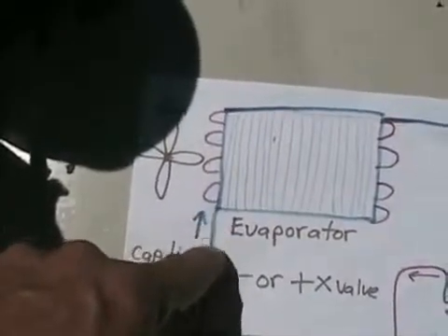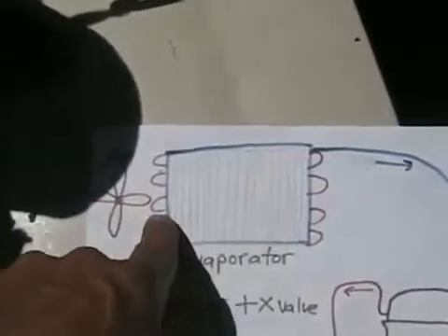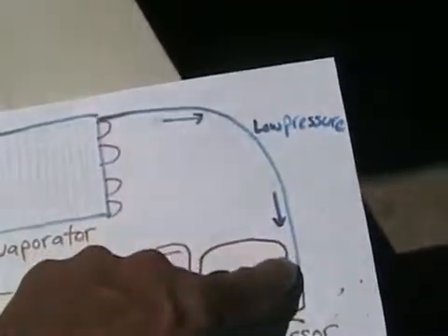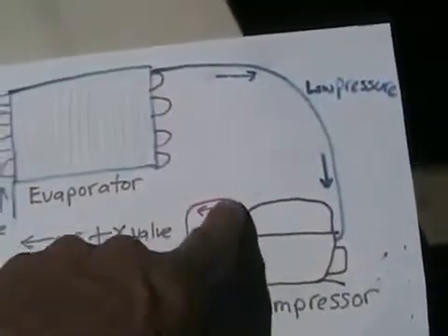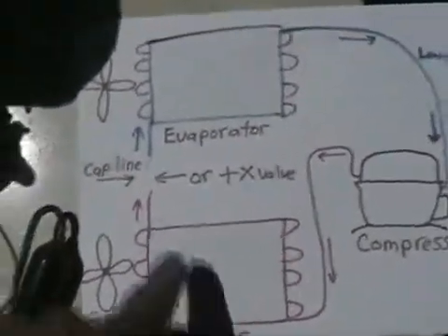So the liquid Freon is now foaming and bubbling as it's going through all these little tubes, and the fan is blowing on the radiator. By the time it gets to the top, or the end of the radiator, it's now a pure gas. The pure gas is now warmed up to whatever temperature the room is where the fan is. And the pure gas goes back to the compressor, now containing quite a bit more heat than it did before, and gets recompressed again. And then the heat, of course, is exhausted by the condenser. So that's how all systems work.